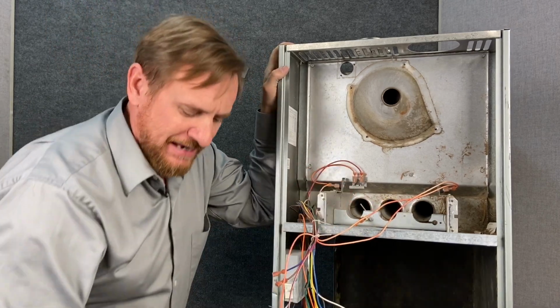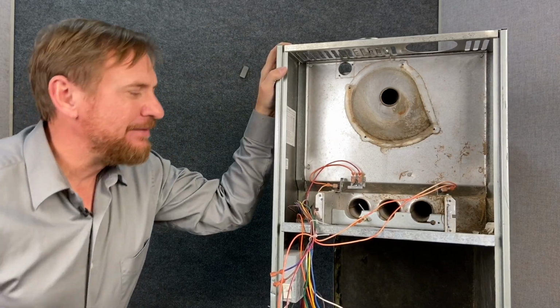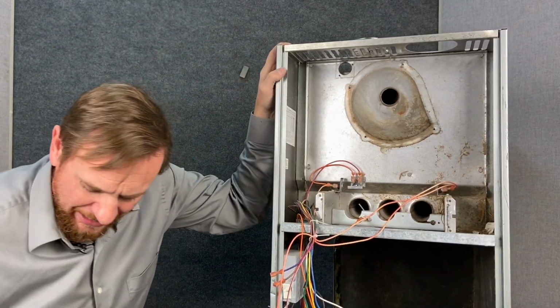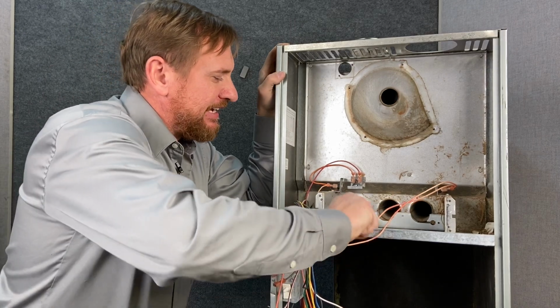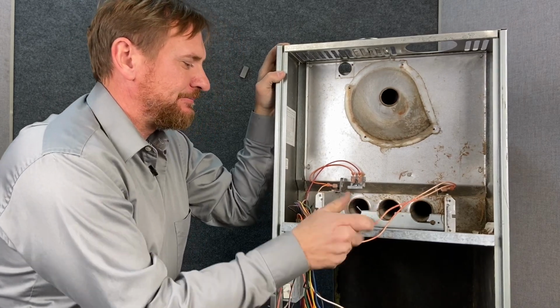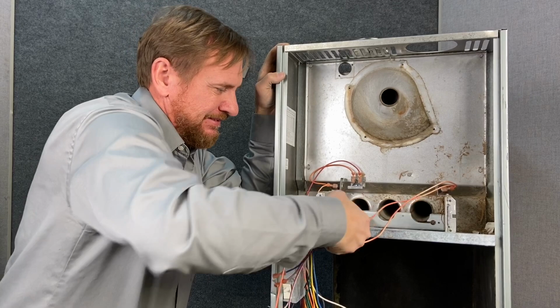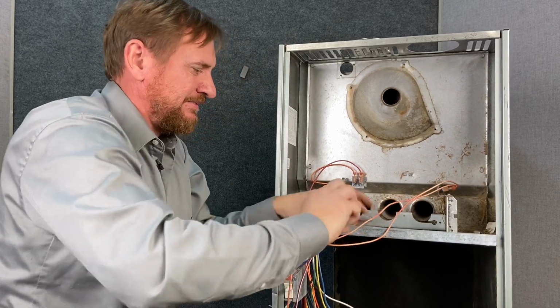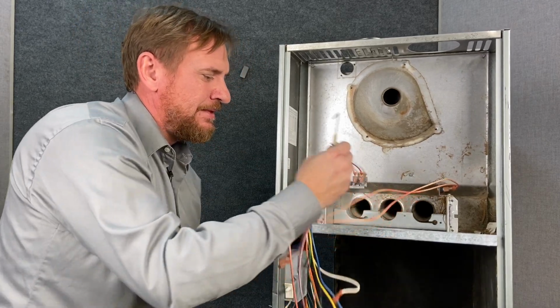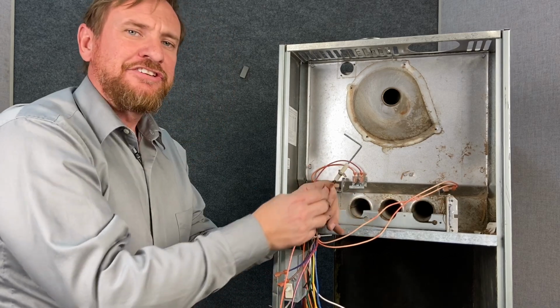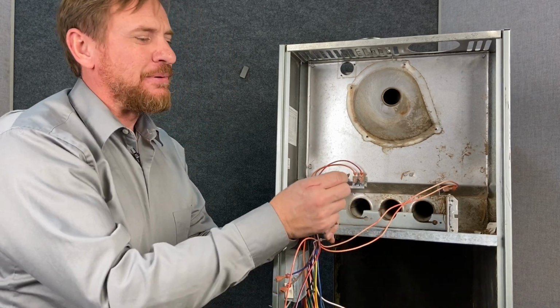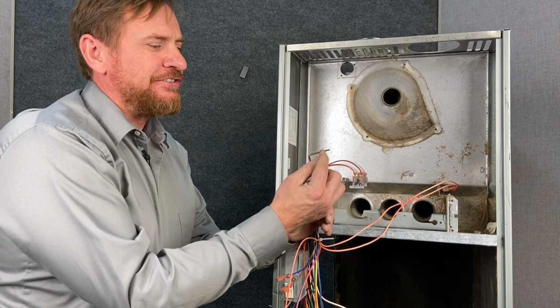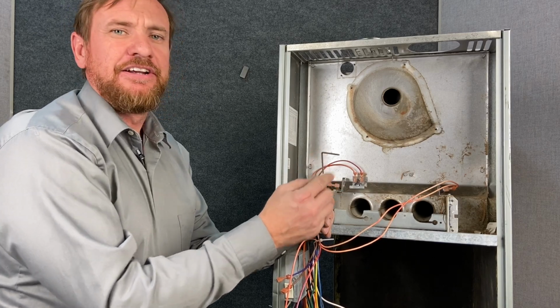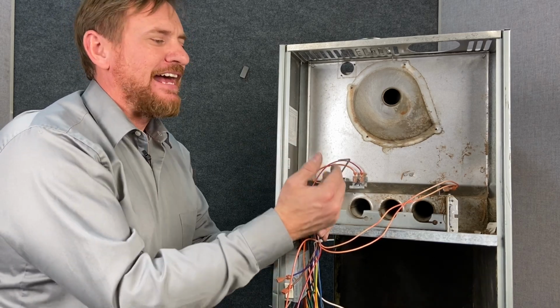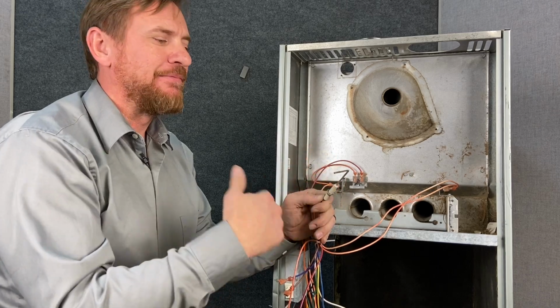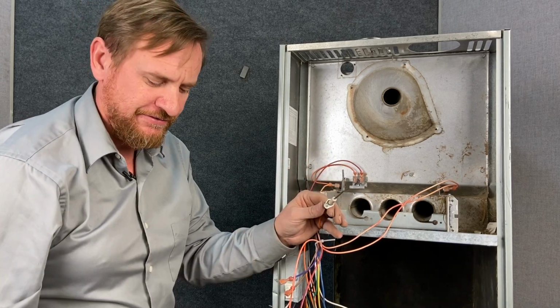The other component we have on the opposite side is our flame sensor. Just one wire on it as well. What we're going to do is we're going to take it off next so we can see that component. This is our flame sensor. It also has to be cleaned the very same way as our spark igniter. We can see all this different discoloration on here and even some rust on there. So that needs to be cleaned off. This has to get a good signal against that flame through flame rectification. We'll talk about it in another video.